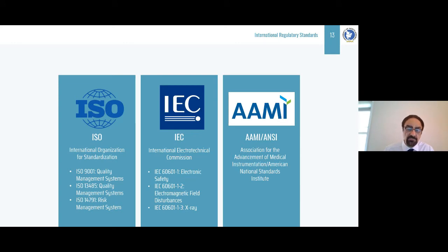submit their documents. Similarly, among IEC standards, we have IEC 60601-1, the electrical safety standard, which is international. IEC 60601-1-2 covers electromagnetic compatibility, disturbances, and others. IEC 60601-1-3 is a standard that oversees X-ray equipment, for example, and other similar standards are also in use.